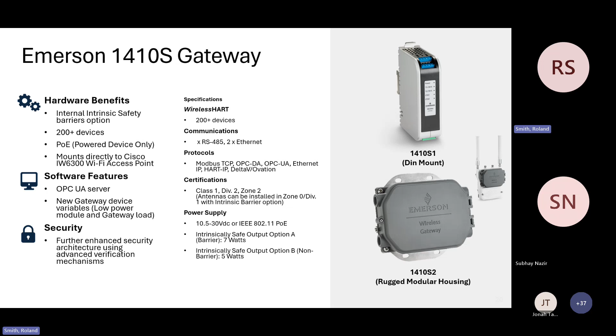There's also a field mount version, a ruggedized housing that can be installed in the field, class 1 div 2 area. On the right-hand side, it's made to integrally mount to the Cisco IW6300 access point. A lot of our customers have remote areas where they'll want to do wireless backhaul, so we mount our gateway on that IW6300 directly. We take the WiHart field device signals into that, put it onto the WiHart or Cisco access point, and seamlessly send that wireless backhaul to another access point at the plant and back into your infrastructure.